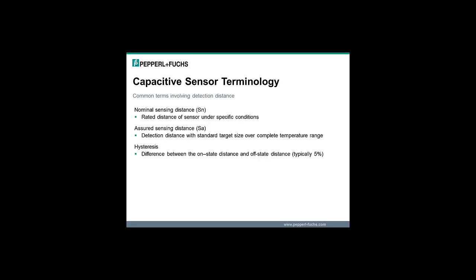Second is the assured sensing distance, which is the distance tested and assured over the complete temperature and voltage range with the standard target size. The assured sensing distance is a more reliable distance to use when designing a sensor for a specific function.